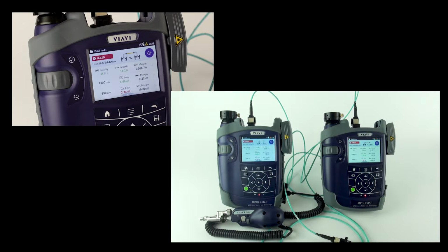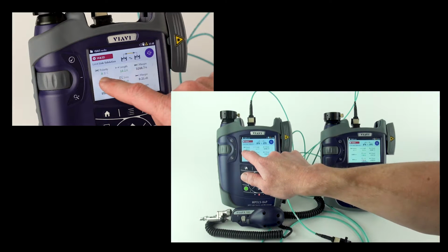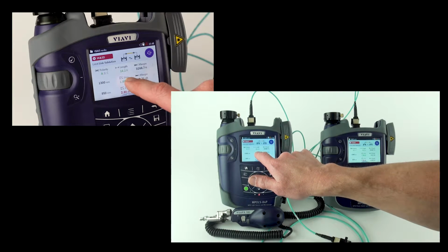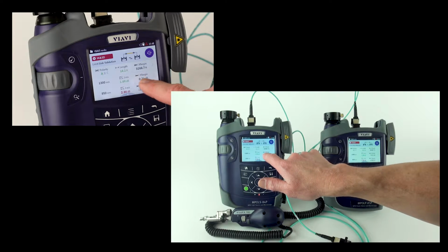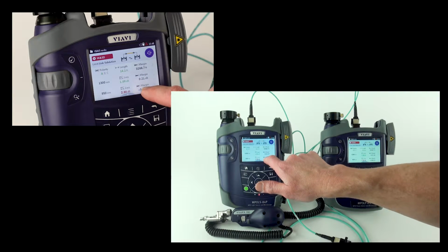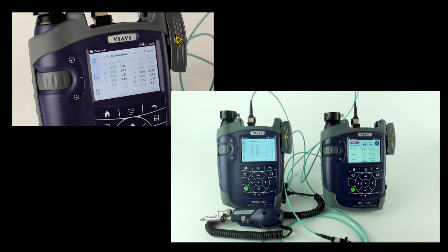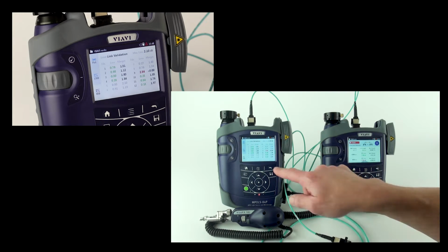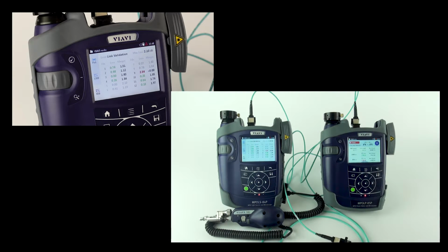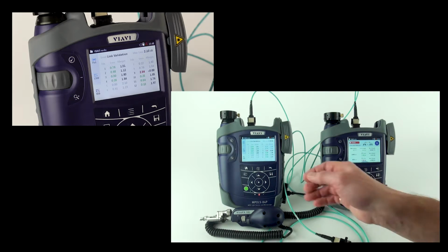And it gives you a fail, and you're able to see the polarity passed, what the length is of the fiber, what your margins are, and you're then able to go into details to see what failed. And in this case, I had one fiber, fiber number 9, that had way too much loss and caused it to fail.